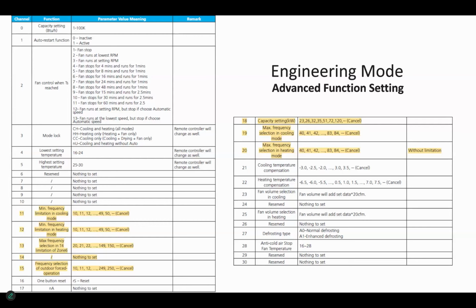But that function is good for situations where, let's say it's in a server room, and we want to make sure that it cannot accidentally be put on heat. Yes, because that way you can set it to cooling only, and that's it, you're done.